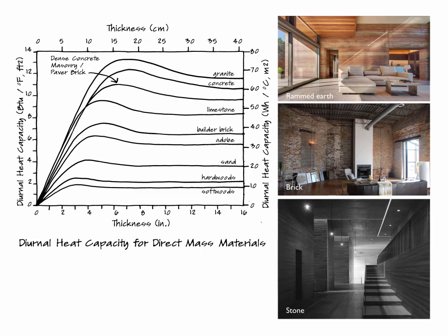So what does that tell us? It tells us that, number one, you can't just keep adding thickness, right? So the volume of mass for thermal storage is sort of less important than the area. And really, what we want is 4 to 6 inches of the material, which is then distributed in as much area as is required to store the amount of heat that we need to store in the building. Okay.